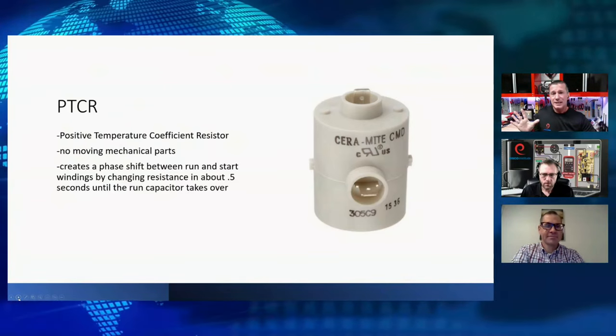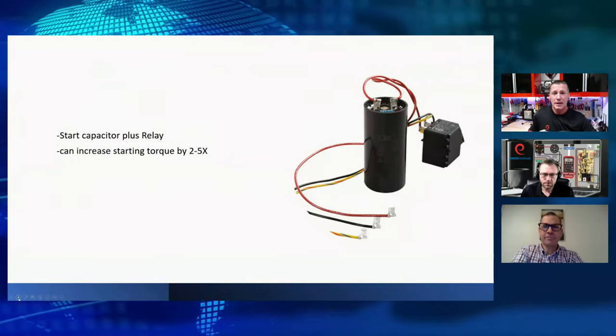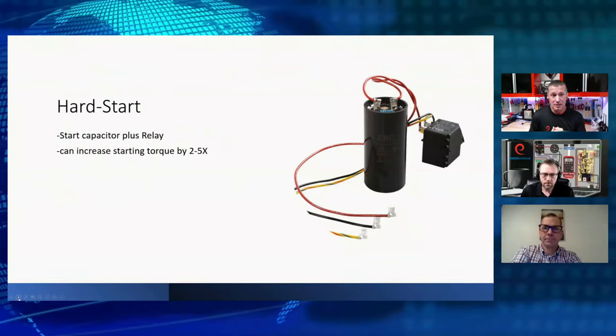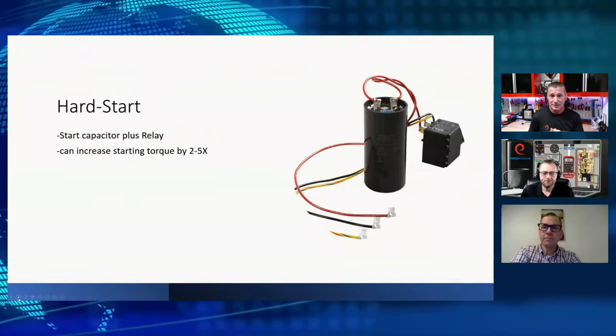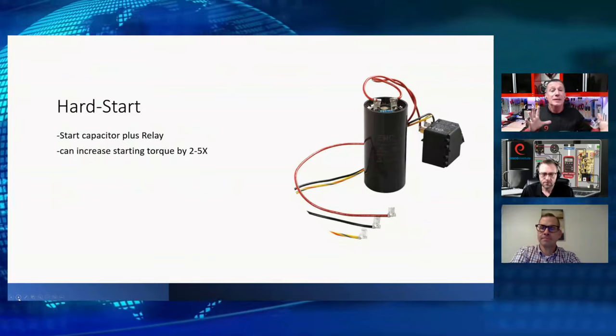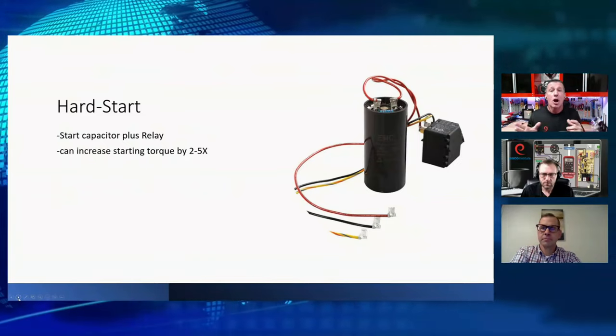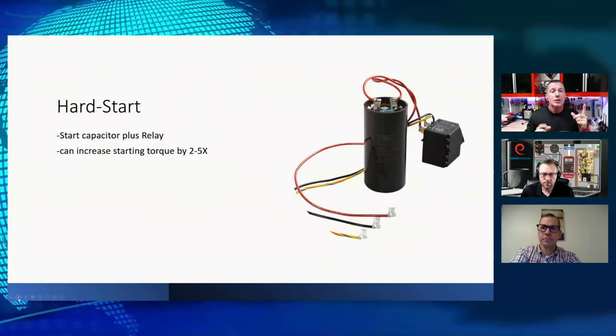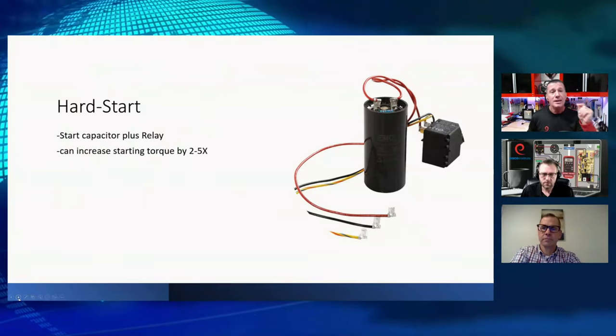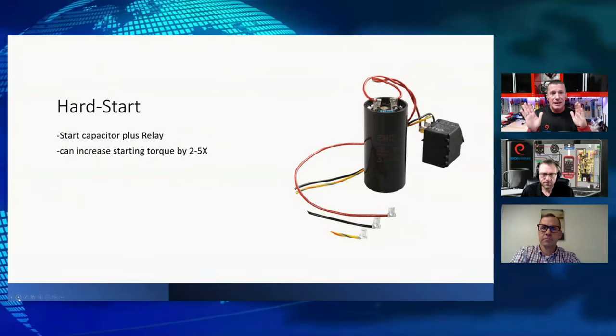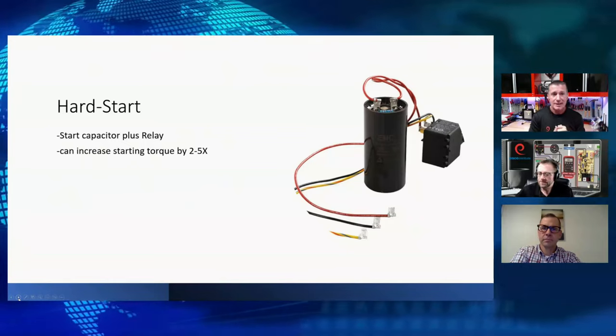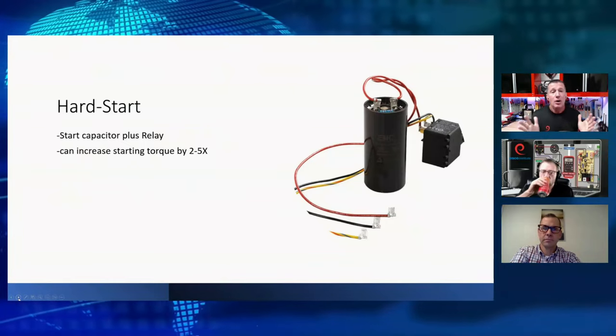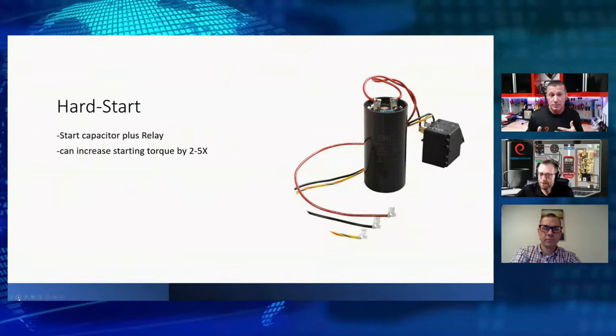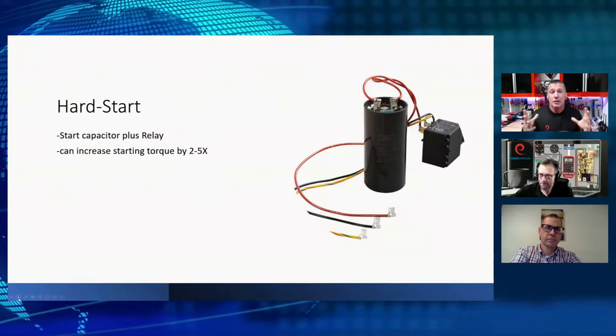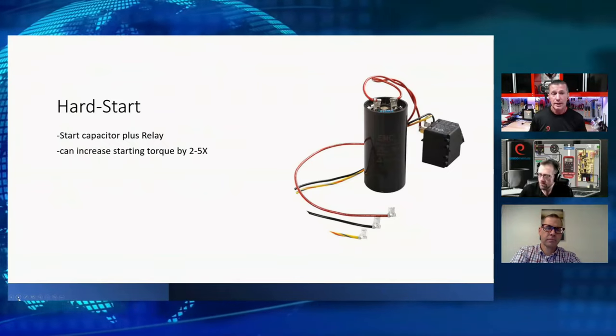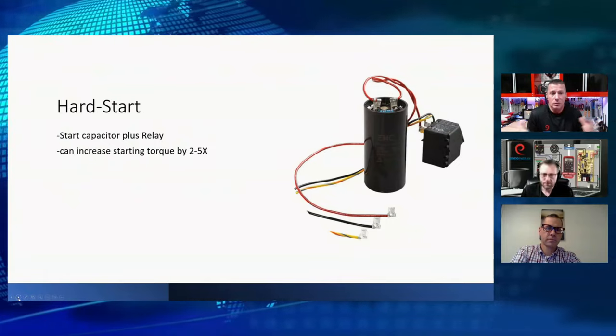So we're going to see PTCRs if you haven't already seen them. We always talk about hard starts because that's a common component in the industry. What we're doing there is simply adding a start capacitor along with a relay so we can engage it for a short period of time to shift that phase and get the motor up and running faster. Used a lot on equipment that's struggling to start, say maybe we've had some insulation breakdown and need a little extra torque on that motor. Longevity is really what it's there for.